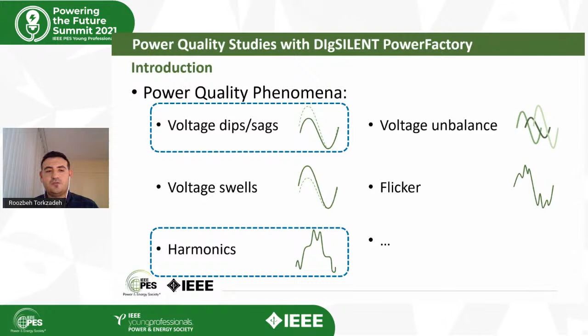But today in this presentation, I'm going to talk more about two phenomena: voltage dips and harmonics. This is because these two are maybe the most important ones, as they can impact both clients and the grid, as well as equipment in the grid and on the client side. Because of the energy transition, there will be changes in the grid, and this may intensify the propagation of voltage dips through the grid, and also the harmonics.